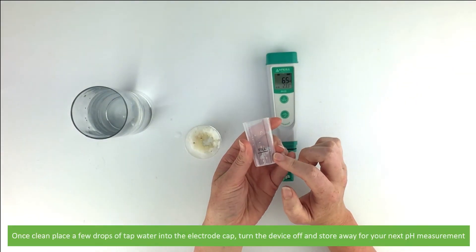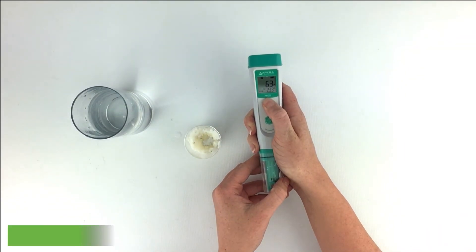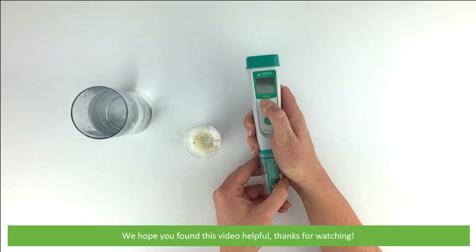Once clean, place a few drops of tap water into the electrode cap, turn the device off and store away for your next pH measurement. We hope that you found this video helpful. Thanks for watching.